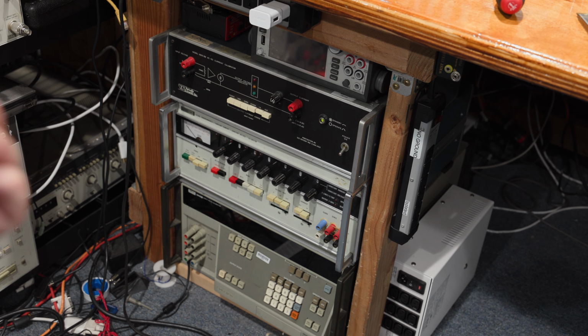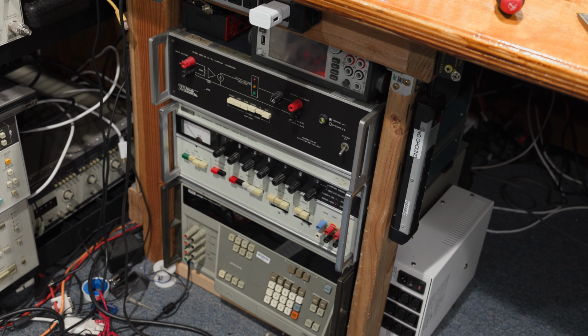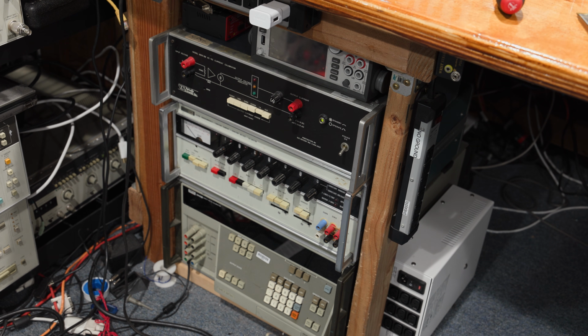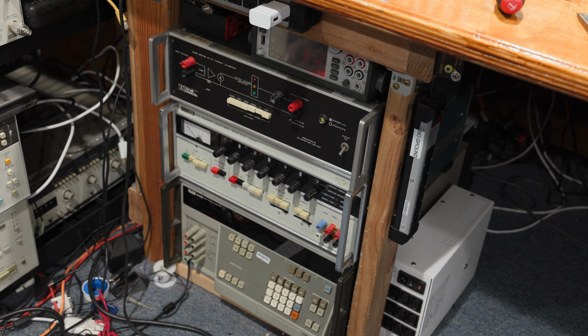The 5440 agreed with the 343, which was my base standard, and it agreed with the 3330, which is also pictured here. So we had three standards that were within tolerances of each other, relatively close. So that's how we settled on the 5440 being the base of the lab so far. Obviously, it still needs to be validated. It can be validated to the calibration and the accuracy of the 7510, which is all I needed at the moment. Might need to be tightened up. Don't know yet because I can't get that extra digit without some better equipment, better meters. Those meters, new, start at the 5-figure mark. So calibration level 8.5 DMMs, the base models start at about $10,000 and go up from there.